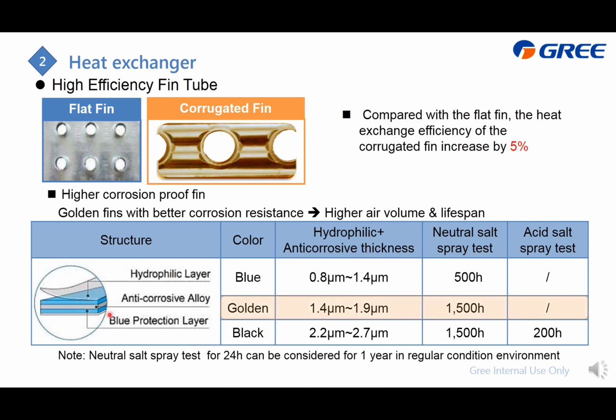Here is the inside structure. Actually, the difference is just the thickness. And if it is thicker, that means the level is higher. The standard golden can last 1,500 hours of neutral salt spray test. If you choose the black one, it has another 200-hour acid salt spray test.